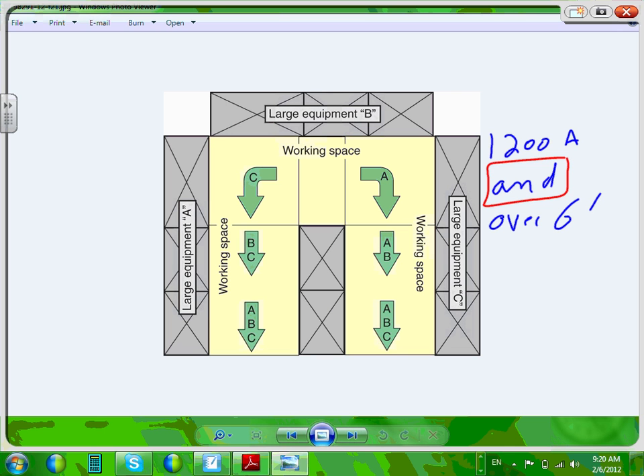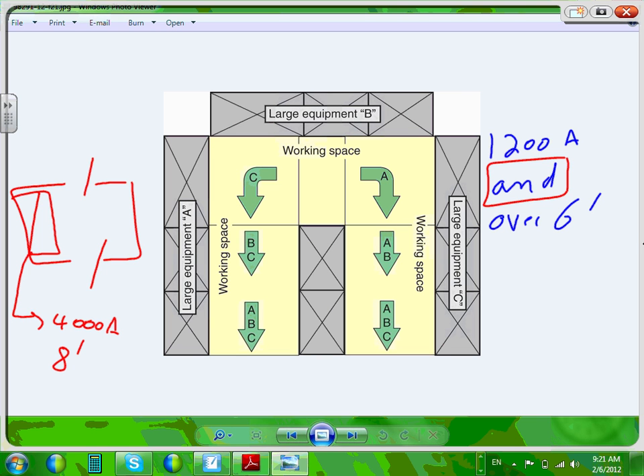You know what the large equipment rule tells you? You have to have 2 entrances to that working space. So if you have a system like this, you have to have 2 entrances, except there's an exception. I want to draw a system like this here. Here's entrance 1, and here's entrance 2, and here's my panel. By the way, my panel is 4,000 amp, and it's 8 feet long. Then I have to have 2 entrances, one on either side of the room.